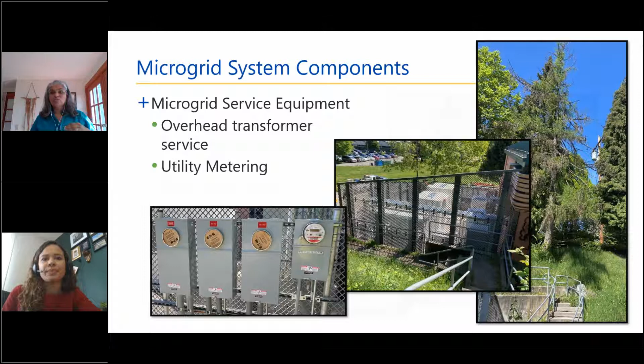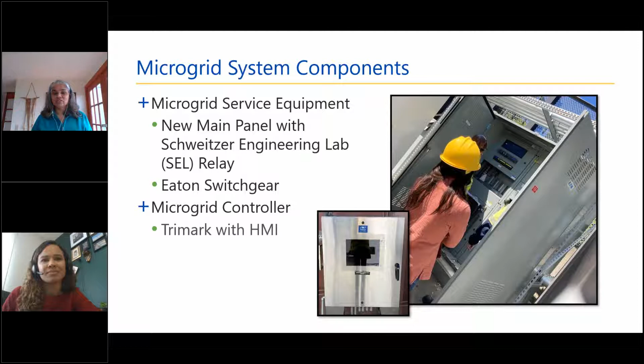Moving down that electrical one-line, this is the main panel board. It has a Schweitzer Engineering Lab SEL 351 relay. The switchgear was made by Eaton, and the microgrid controller is by Trimark, where their HMI, human machine interface, is located, in the stainless steel box. Most of this was NEMA 3R and stainless equipment. It's an outdoor location, so we were cognizant of that and made sure the design kept what was appropriate for those locations.